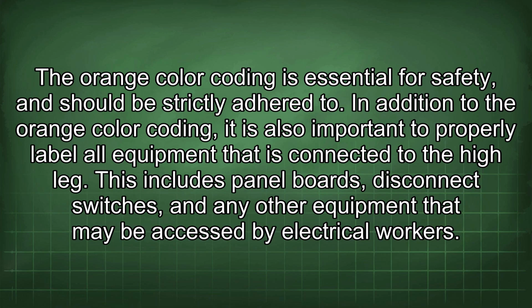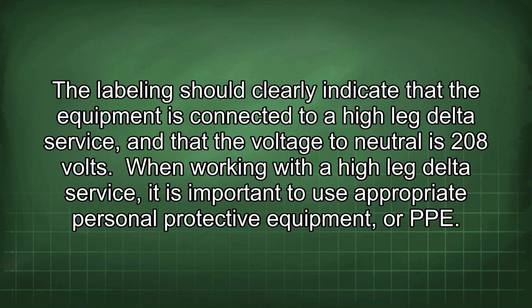In addition to the orange color coding, it is also important to properly label all equipment that is connected to the high leg. This includes panel boards, disconnect switches, and any other equipment that may be accessed by electrical workers. The labeling should clearly indicate that the equipment is connected to a high leg delta service and that the voltage to neutral is 208 volts.